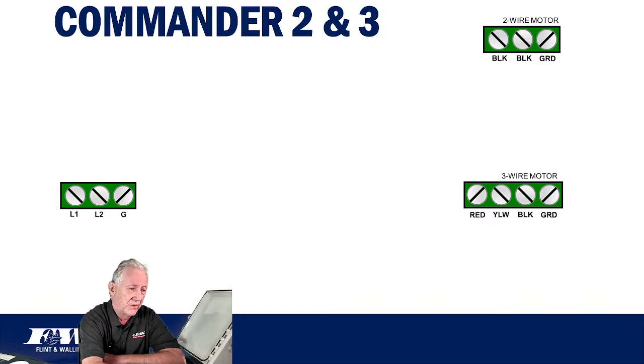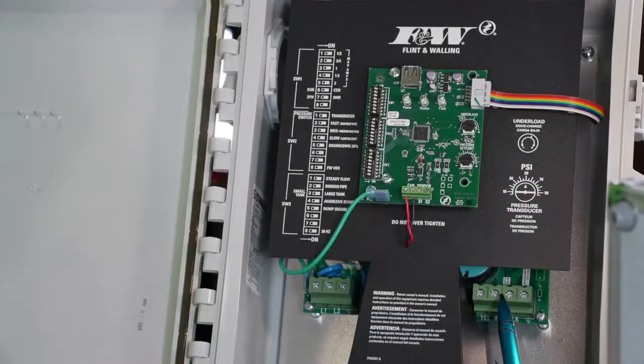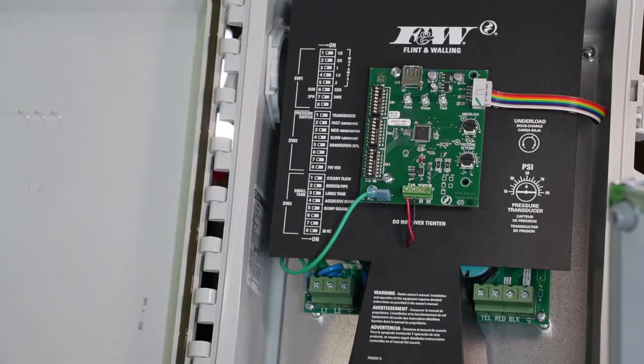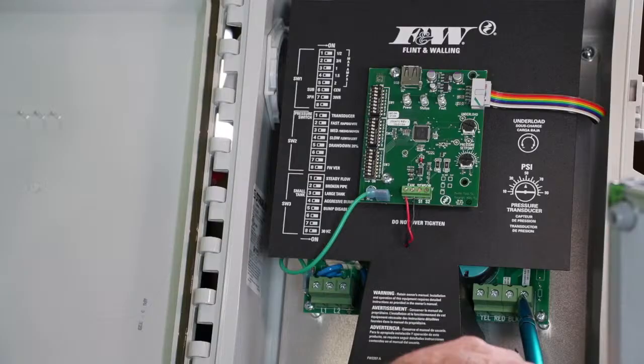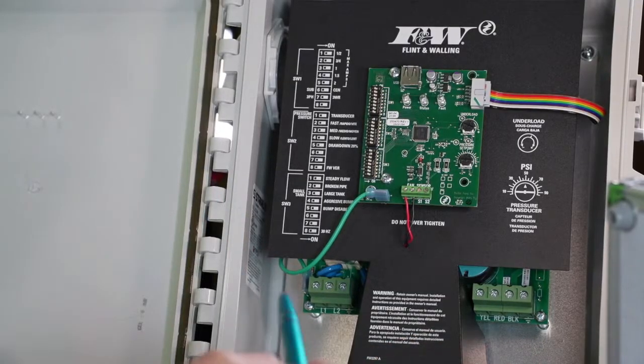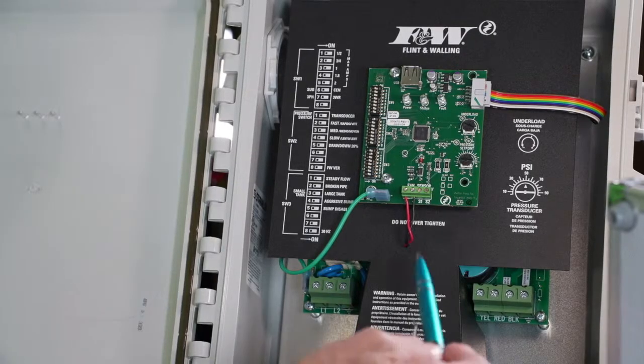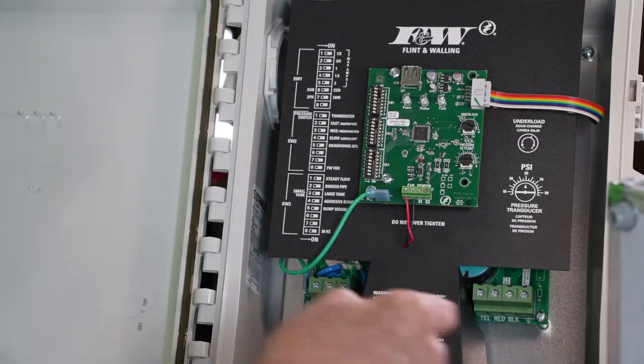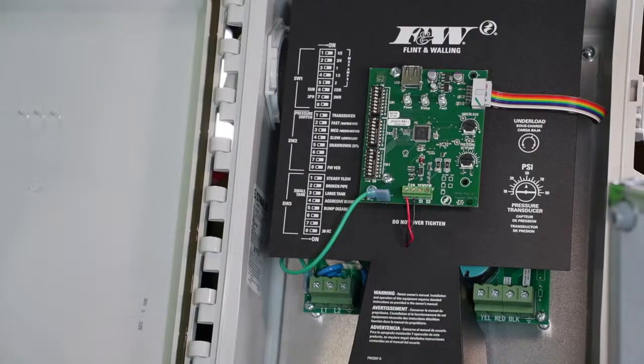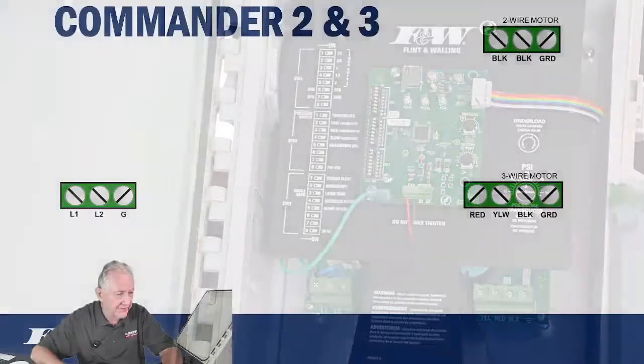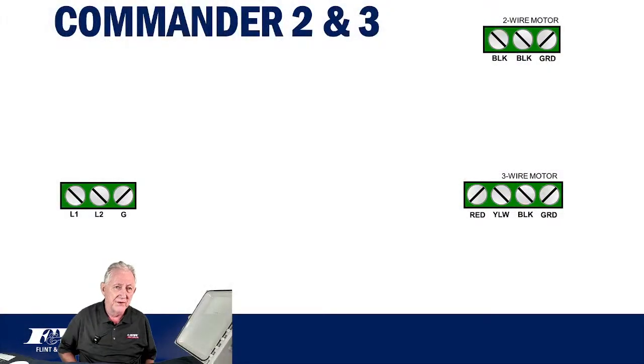So, for example, the Commander 3, you're going to have four terminals over here. You're going to have your red, yellow, black, and your ground. So you'll have 4 terminals over here to run out to your pump motor. If this were, in fact, a Commander 2, then you'd only have 3 terminals over there because, again, with a 2-wire motor, you've got 2 black leads and a green ground. And so that would be one of the differences between the Commander 2 and the Commander 3.